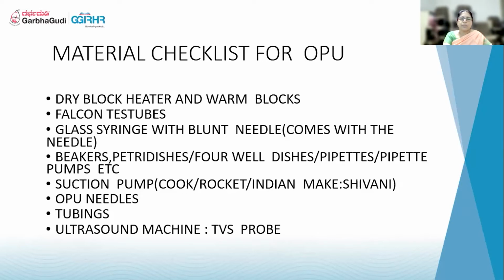Good glass syringes with blunt needles should be kept ready in case the suction pump is not opening or not working properly. Your embryologist will keep all the beakers, petri dishes, four-well dishes, and all the consumables properly. Suction pump should be of good quality like Cook, Rocket or the Indian make Shivani. Don't compromise on that because it will just give way when it is most needed. We always keep one backup suction pump with us because we cannot take risk in this. If the suction pump doesn't work and you don't have any other method to suck, the entire IVF procedure goes to waste. Buy proper OPU needles. There are many marketing people who will give you very cheap OPU needles, just half the cost, one-third the cost.